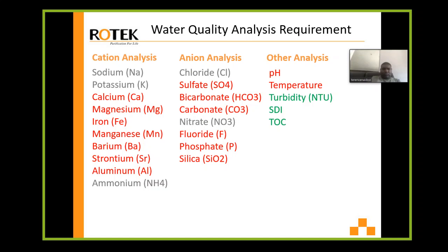And I looked at the complete process. Because river water has high turbidity, they have sedimentation designed before entering the sand carbon filter, and in the sedimentation they use lime, coagulation and flocculation in the process. And I asked, okay, what kind of flocculation are they using? There are two types of flocculants, PAM and PAC. Okay.